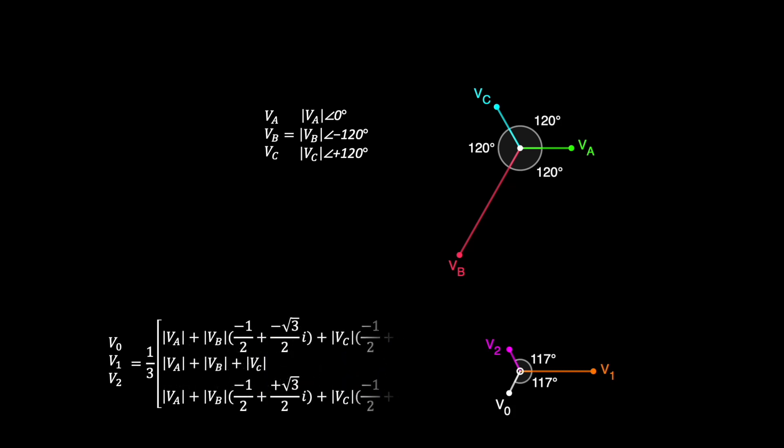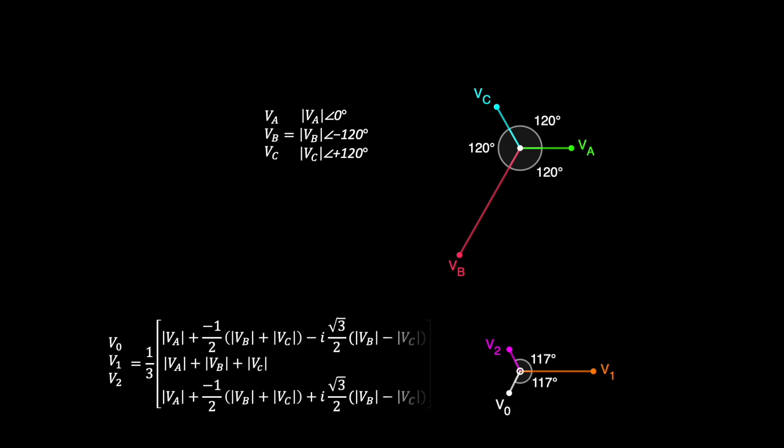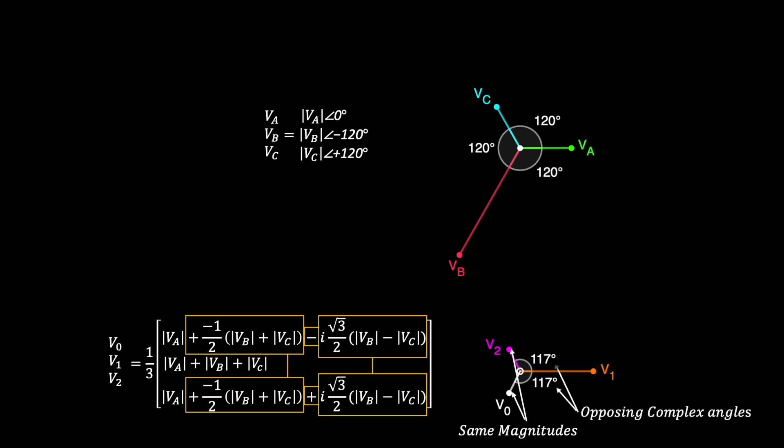And then after doing a little rearranging, I can isolate the imaginary value in the equation. After doing this, the V0 and V2 phasors show the same terms for their real and imaginary components, which means they have the same magnitude. But the imaginary terms have opposite signs, which makes them mirror each other on either side of the positive sequence phasor.